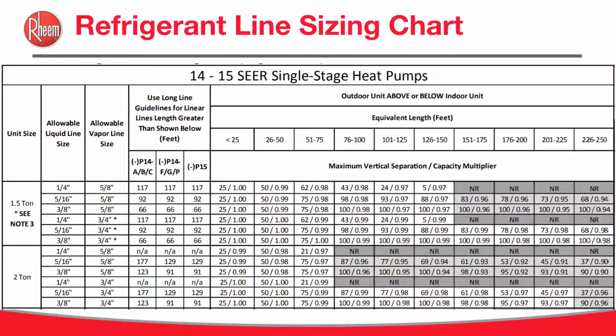We need to properly size the lines. This is to reduce the possibility of flashing of refrigerant. This, however, can be caused by several reasons, including low charge, improperly sized lines, heat absorption along the line, and or excess vertical rise. We all know the maximum pressure drop allowed between the condenser and the evaporator is 50 psi. The suction line. The suction line is used to transport superheated vapor to the compressor. Suction line sizing is important for capacity as well as oil return to the compressor.